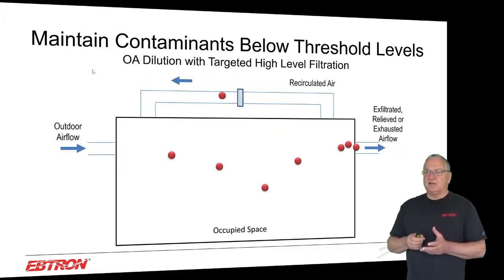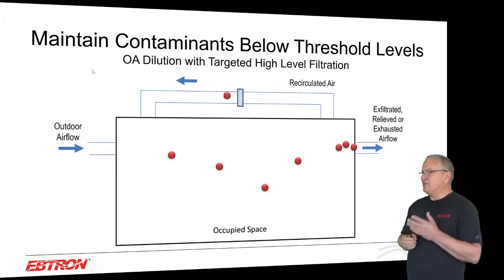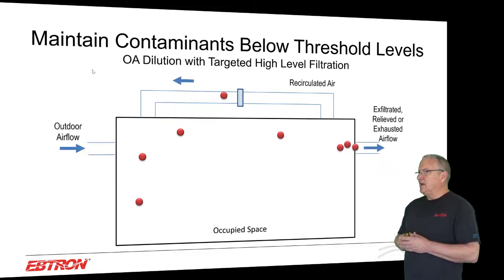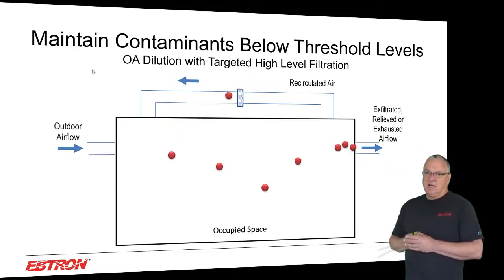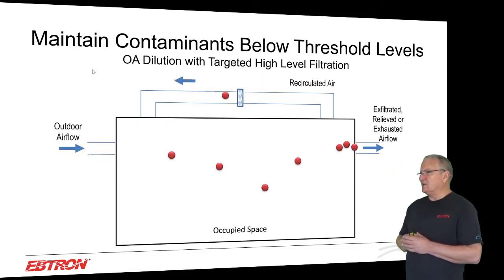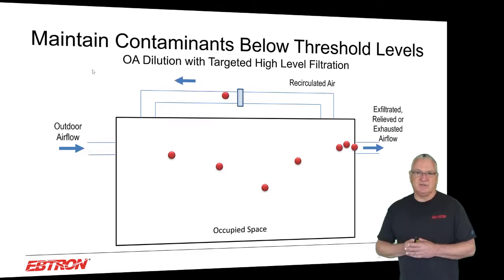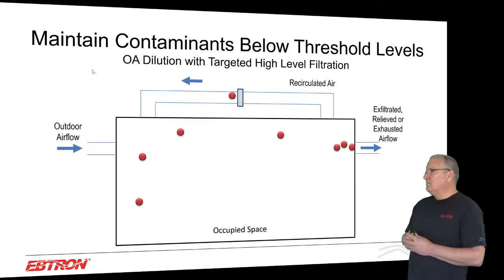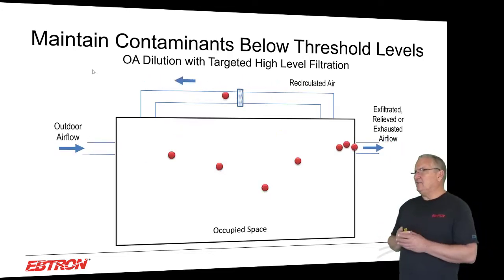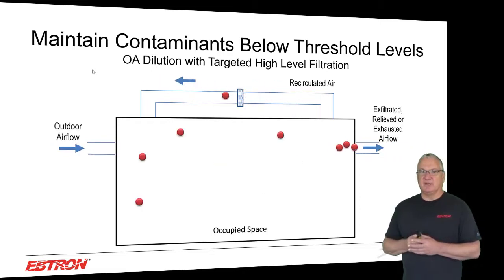Ultimately what you want to do is a combination of outdoor air for dilution and recirculated air that gets filtered. I'm very concerned about people who are saying, let's put in some air cleaning equipment and reduce the outdoor air — I think that's really dangerous and foolish. The idea of using high-level filtration and outdoor air together, the combination of the two, is really what we're going to do.